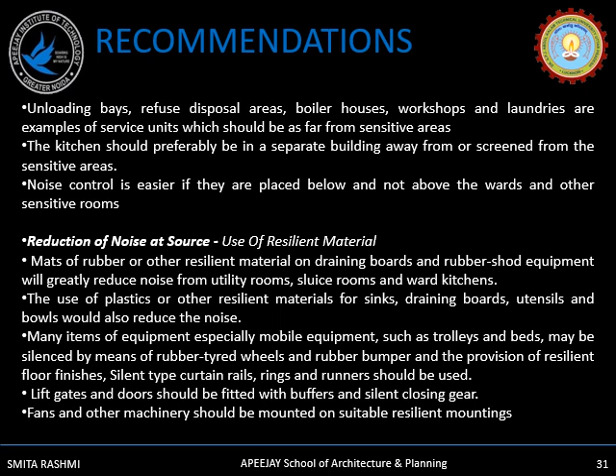With so much use of heavy machinery and equipment, noise reduction at the source level is very much desired in hospitals. For that, resilient material is to be used. Mats of rubber or any other resilient material will greatly reduce the noise from the utility rooms, and mobile equipment can be silenced by means of rubber tired wheels and provision of resilient floor finishes. Doors and lift gates to be fitted with resilient closing, that is soft closing gears. Fans and other noise generating machines to be mounted on suitable resilient mountings.